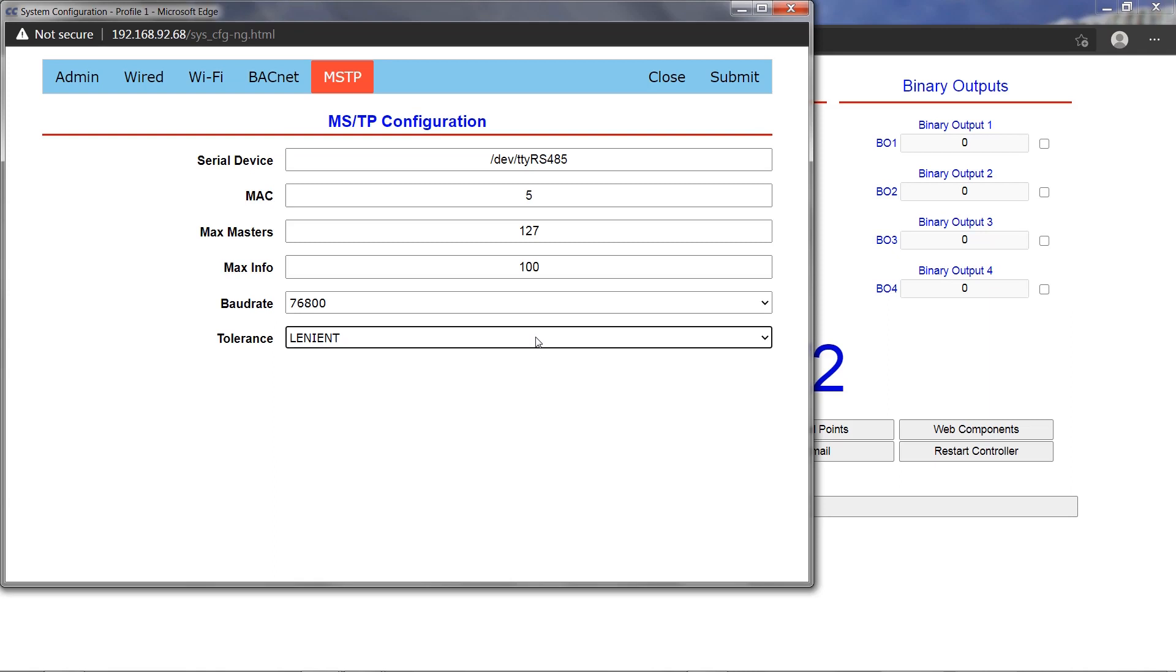The baud rate must be set to match the baud rate of the devices on the connected serial network. The tolerance can be set to lenient or strict, however lenient is the recommended and default setting. When finished with configuration, click the submit button at the top to apply changes.